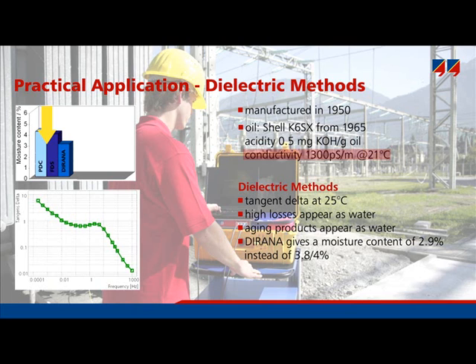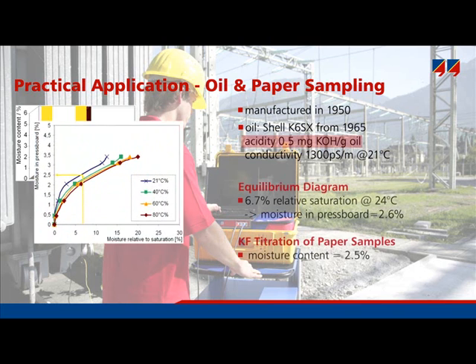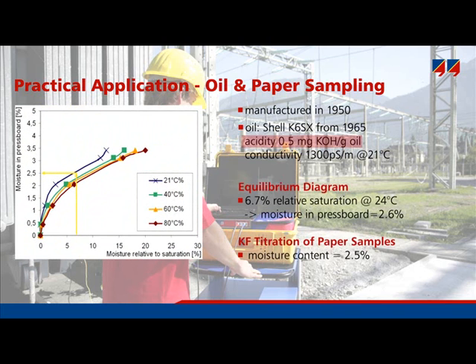DIRANA calculates more reliable results that are typically in a similar range to those from the paper samples taken from the transformer. Unfortunately, aging makes the application of the old equilibrium diagram based on PPM moisture content impossible, as it causes the equilibrium curves to shift towards the oil, resulting in an overestimation of the moisture content. The new equilibrium diagram based on relative saturation indicates a moisture content of 2.6%, which agrees well with the value of 2.5% derived from the paper samples and the DIRANA reading of 2.9%.